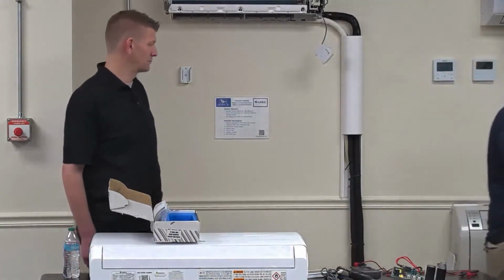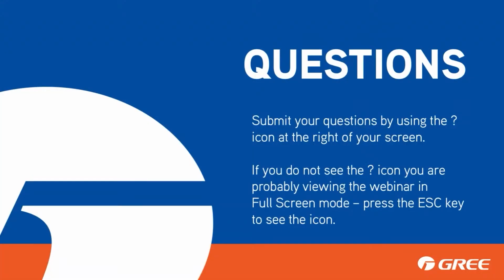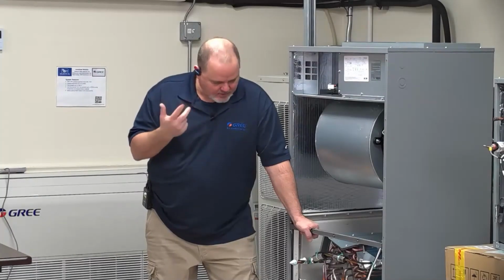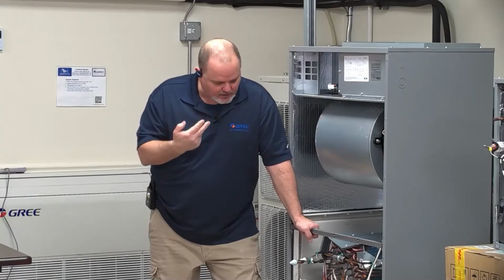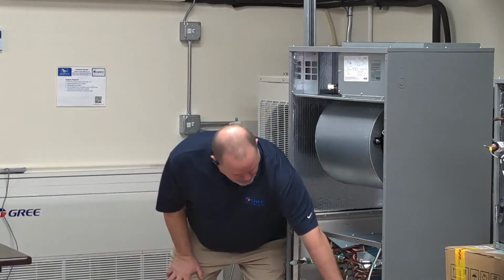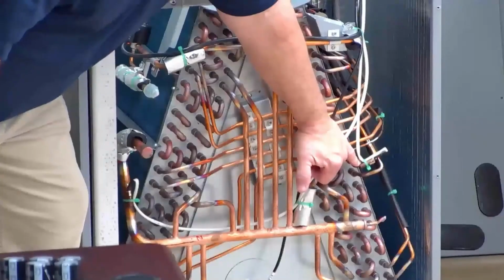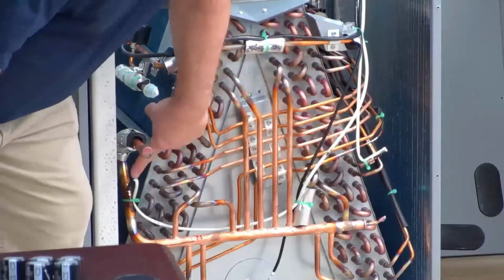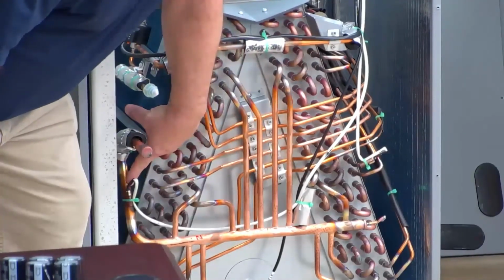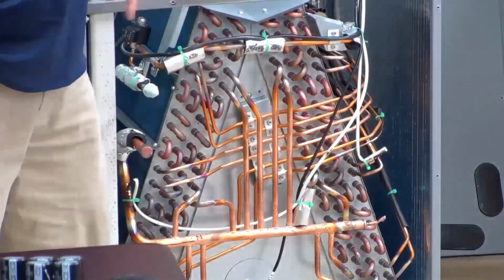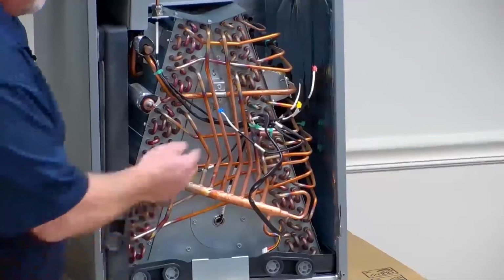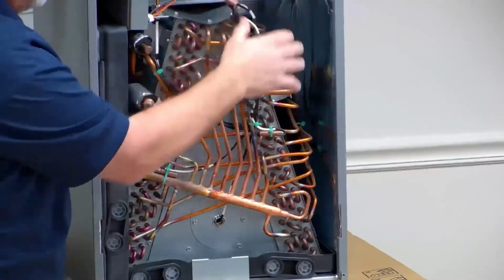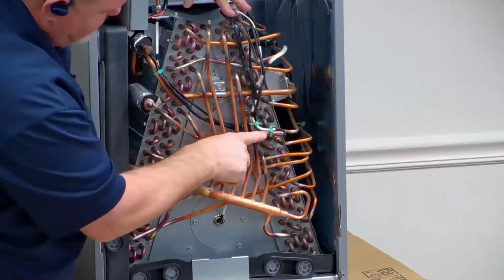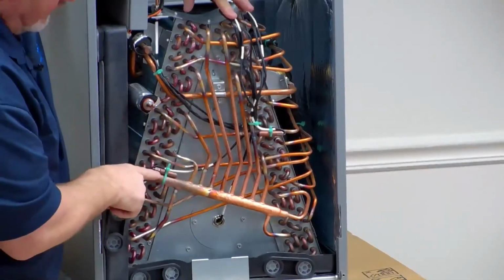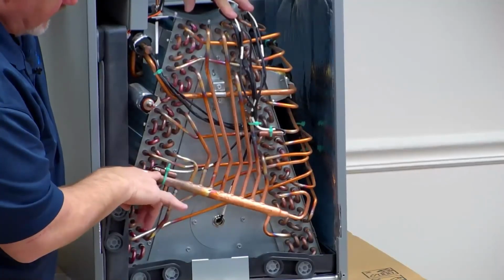All right, so now I want to redirect your attention over here to these couple units that I have, just like the wall mounts, the ducted, the cassettes, all of them. As I said earlier in the piping diagrams, you have an inlet and outlet temperature sensor. So right here is the inlet temperature sensor coming from our refrigerant feed in. And then here is the outlet right on your gas pipe coming out. And then so I don't have to be bent over anymore, I'm going to come over to this other coil. I got the whole control panel taken off here just for show and tell. But here's our inlet pipe temperature sensor. Here's my outlet pipe temperature sensor. So they're a lot easier, a lot closer together on this particular coil.